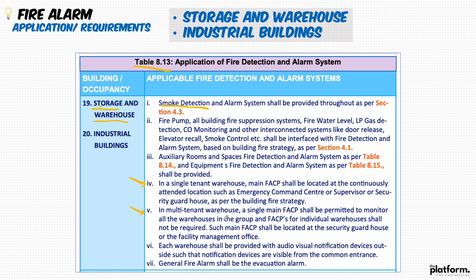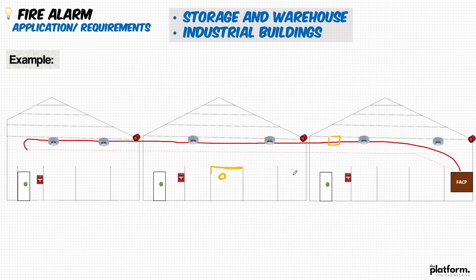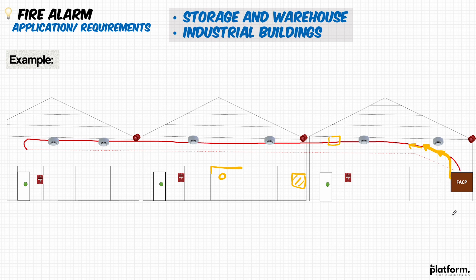For a multi-tenant warehouse, a single main fire alarm controller shall be permitted to monitor all warehouses in the group, and a fire alarm control panel for individual warehouses shall not be required. So if you're working on a project with multiple connected tenant warehouses, you don't need a separate fire alarm control panel in each one — one controller can monitor all connected warehouses together. That panel should be in the facility management room, security guard house, or an attended location, serving as the master panel for all warehouses.